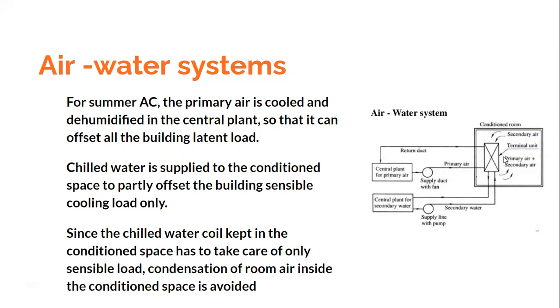You know that in air conditioning, you are handling both the loads, the sensible load as well as the latent load. So the purpose of the primary air is to handle the building latent load. Okay, and then in addition you have the duct layout as well as the pipe layout here. So what would the pipe do? The pipe would supply the chilled water here, and the chilled water would offset the sensible cooling load. So water is going to offset the sensible cooling load, and air is going to take care of the latent load. So you would have a ducting system as well as a piping system in this plant.